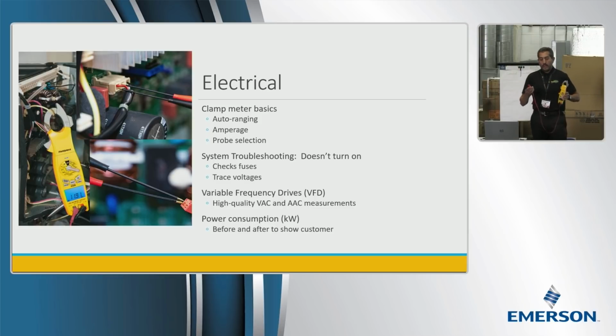A good way to do it is use a couple alligator clips. Clamp onto the incoming voltage at the outdoor unit, L1 and L2, and then take your clamp meter and clamp it on either the L1 or L2 wire. Doesn't really matter, and then the meter starts displaying kilowatts in real time.